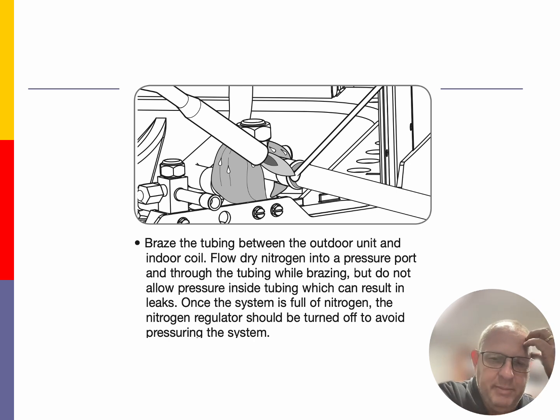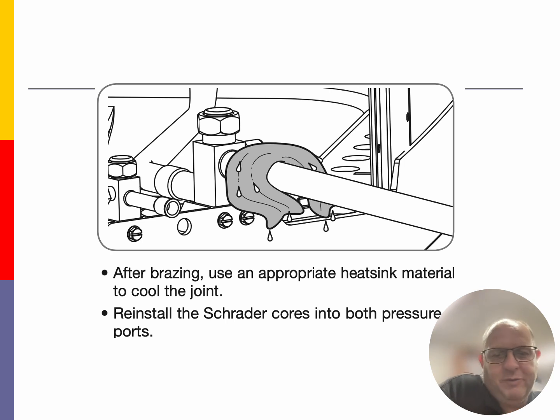So as you are brazing, make sure that we're filling that entire cavity up with our braze rod, and that we're keeping that towel or that moist rag wet with a spray bottle so that we do not hurt that valve itself. So after you get done brazing on that unit, we want to wipe it down and try to cool it off as fast as we can.